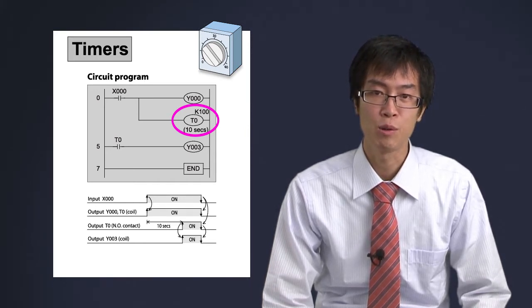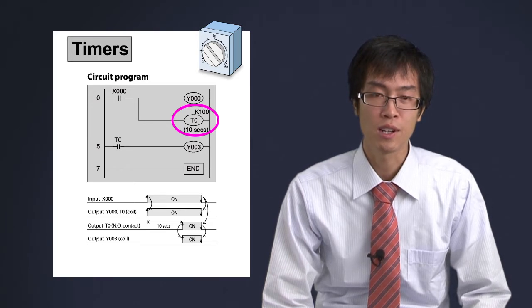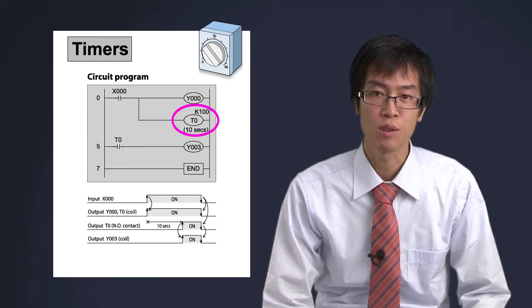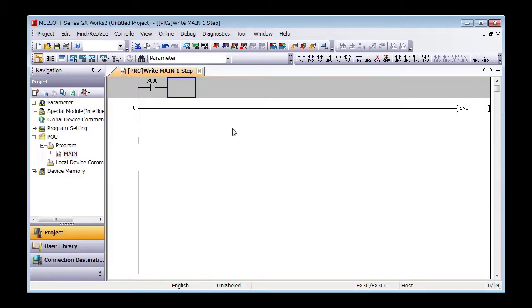For example, if you set timer T0 as 100, T0 contact will not turn on until after T0 coil has been energized for 10 seconds. This is used to program a delay.